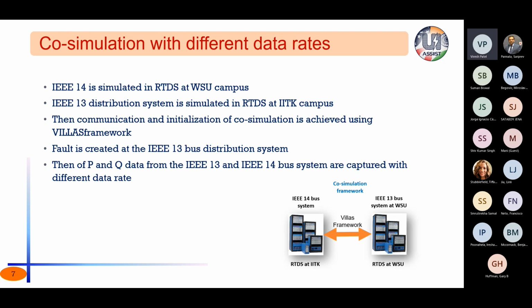And then the co-simulation with different data rates was performed. First, the IEEE 14 bus system was simulated, and the voltage, frequency, and phase was sent to the IEEE 13 bus, which was simulated at WSU. And then the real and reactive power from the IEEE 13 bus is sent back to the IEEE 14 bus system, and then the communication is established using the VILLASframework, and the whole system is up and running.